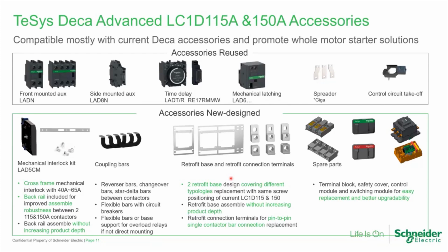So you don't have to drill them again if they are mounted on screw. You can simply use this retrofit base and convert it to new contactors. As a spare, we have Everlink and lugs available with us. In fact, if you are going with lug connection and need to protect them with IP20, we can provide you spares for this, which will make your contactor IP20 again.